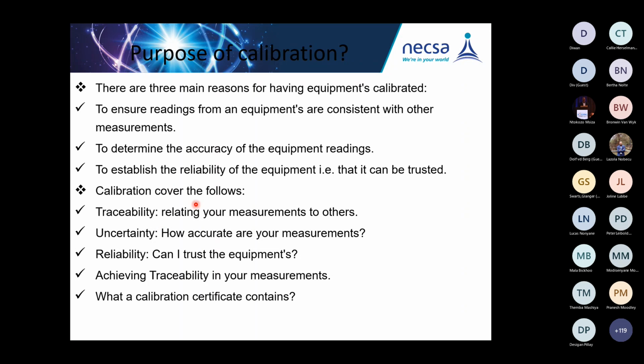This is the reason why we are supposed to calibrate our instrument: to ensure the readings from the equipment are consistent with other measurements. Who are the other measurements? The national measurement standard. A calibrated instrument's reading should be more or less the same as another calibrated one, but differ by a percentage, with the uncertainties from the calibration point, where, as my colleague was presenting, it gives the upper and the lower limit.